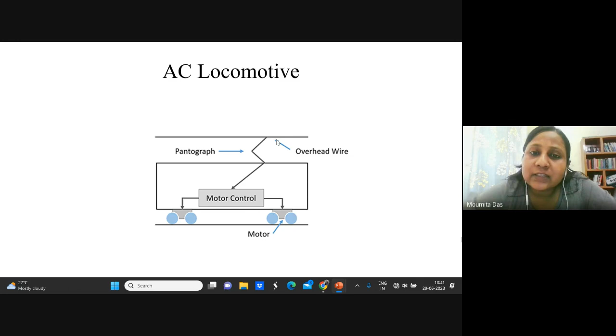So a power electronics transformer is basically where the transformer is placed in between converters, and the converter can operate at high frequency. Depending on that, the transformer will be high frequency in nature. So a power electronics transformer can also be known as a medium frequency transformer. It can operate from a few tens of hertz to a few hundreds of kilohertz. So that is a medium frequency transformer.